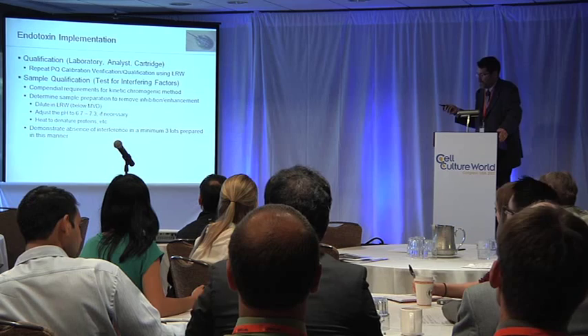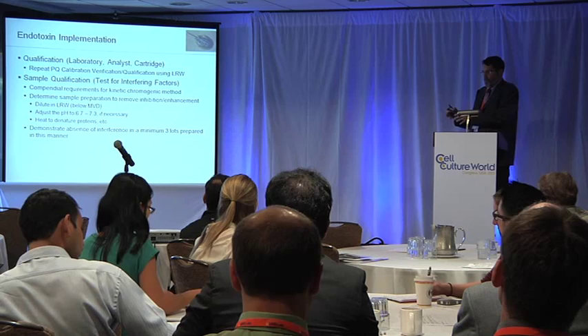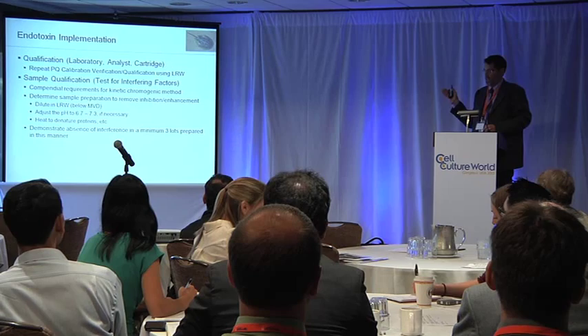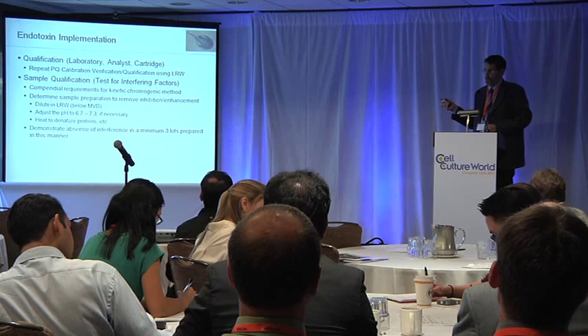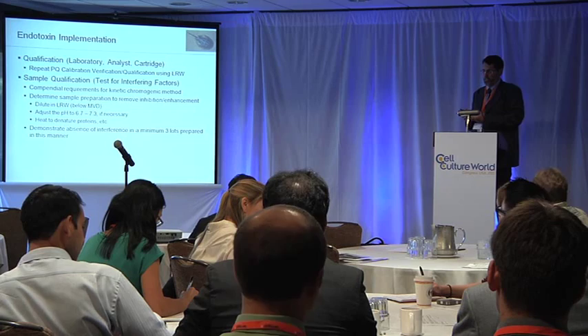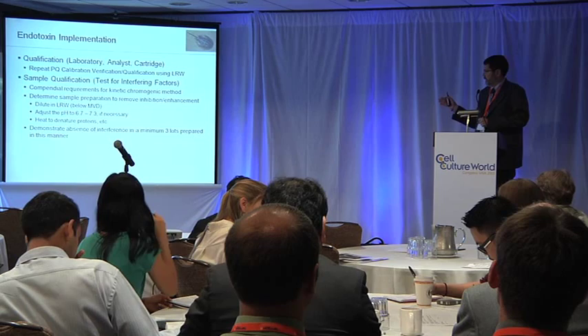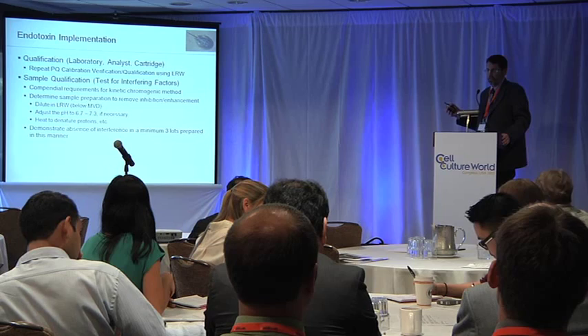For implementation, the best thing about this test is that even though it's automated and handheld and in a little cartridge and looks completely different from any other endotoxin test you might do, this is the kinetic chromogenic method that's in USP <85> and the European Pharmacopoeia. We've gotten confirmation from regulatory agencies that this is the kinetic chromogenic method — no additional testing is required to show comparability. You just do what you would do for the kinetic method, with a sample qualification requirement to show that it doesn't interfere with your test.